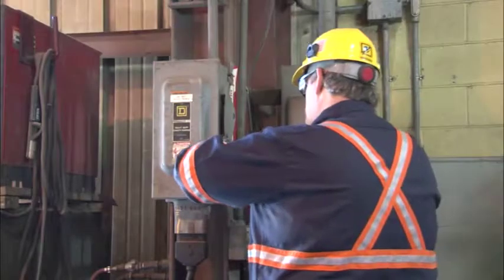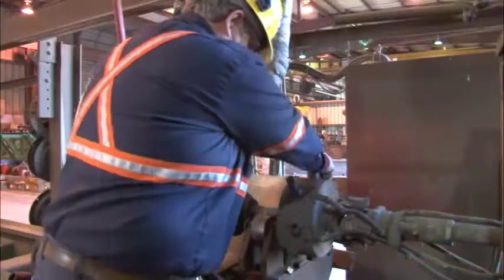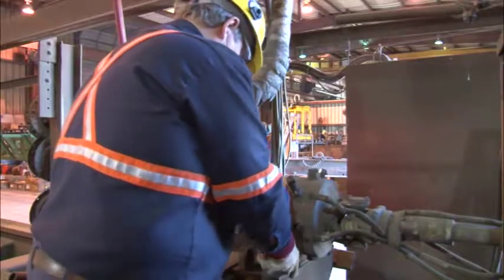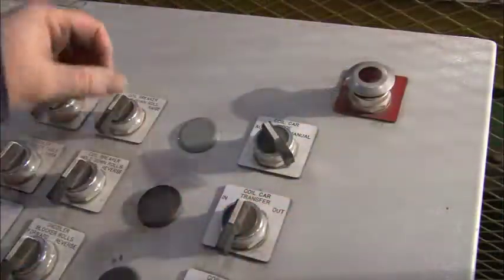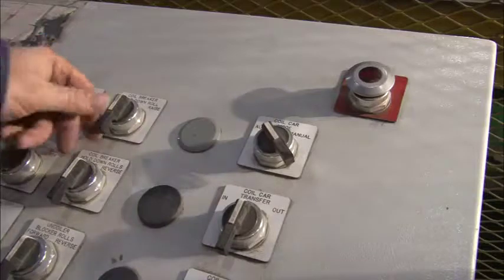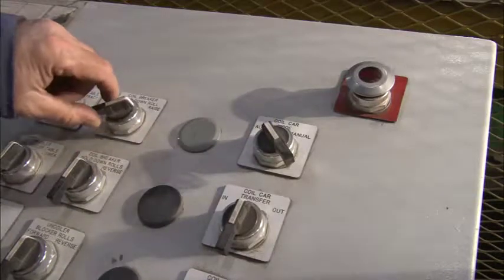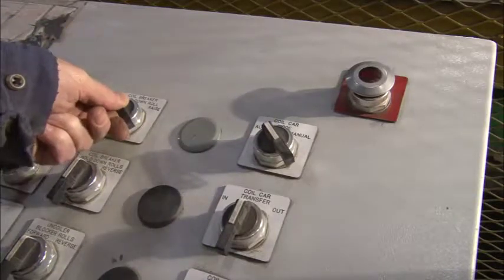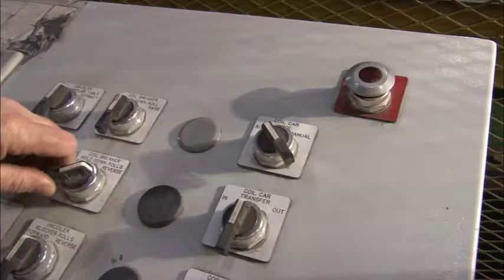This employee did not try out or verify that the equipment is in a zero-energy state prior to starting work. Tryout will indicate if any errors were made during the lockout process. This very important final step of the lockout process must never be skipped.